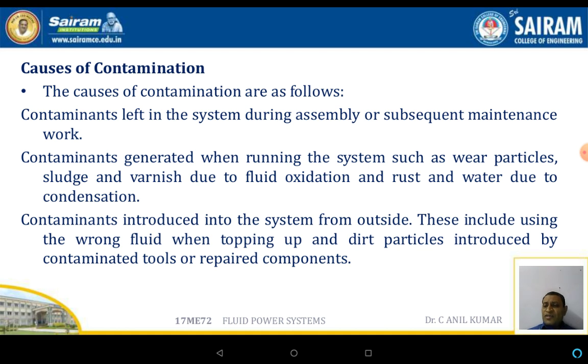The causes of contamination are as follows. First, contaminants left in the system during assembly or subsequent maintenance work. Second, contaminants generated when the system is running, such as wear particles, sludges, varnish due to fluid oxidation, rust, and water. Third, contaminants introduced into the system from outside, including using the wrong fluid when topping up, or dirt particles introduced by contaminated tools or repair components.